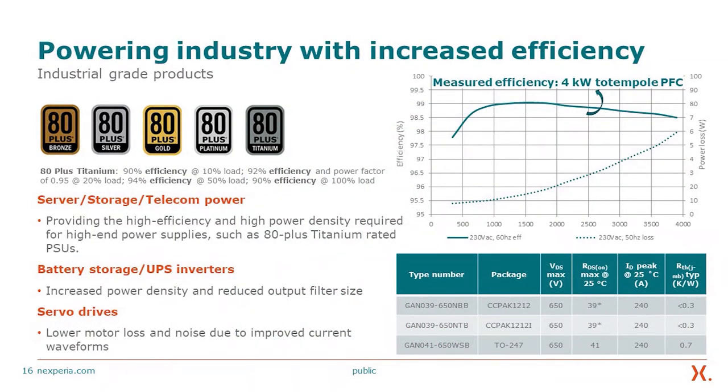Looking at industry efficiency benchmarks, these products deliver in excess of 99% efficiency in a 4 kW totem-pole PFC configuration. The 80 Plus standard is an industrial-grade benchmark, and gallium nitride power technology reaches the highest tier: 80 Plus Titanium. The 80 Plus Titanium requires 90% efficiency at 10% load, 92% efficiency with power factor of 0.95 at 20% load, 94% efficiency at 50% load, and 90% efficiency at 100% load — all of which are met by this power GaN technology.